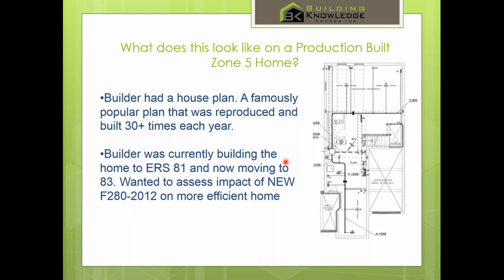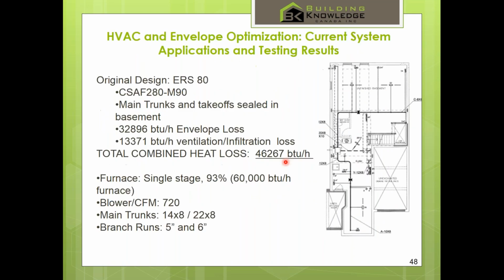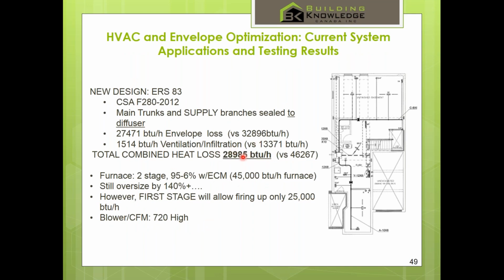Real quick in action, this is a couple of sample homes we've done. This was a house that a builder had built, and they wanted to move to building better than code, so they went from 80 to Energy Star 82 83. They used the new F280 in the house. This is a production builder. Originally, the house had about a 46,000 heat loss on it, a 93% efficient furnace with 22 by 8 size trunks with 5 to 6 inch mains. And when we redesigned the home, the total combined heat loss dropped down to 28. That was with a little bit more insulation, using the new F280 and using better air tightness, 2.5 ACH when tested with the blower door. So all of a sudden, we had to use a two-stage unit just to enable the lower stage to meet the main load of the house.